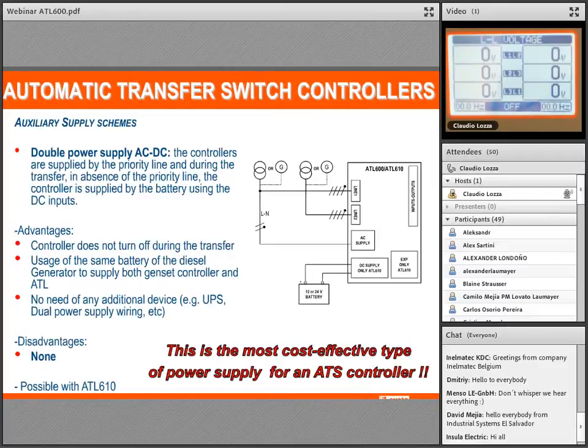What does it mean? The AC supply is present from the line 1 or the primary line, because you can select the primary line inside the setup. So the controller doesn't turn off during the transfer, because when the primary line is absent, the controller changes the power supply from the AC side to the DC side. So the battery is not used if the AC is present, but is used only in case of emergency, so during the transfer. So there is not any disadvantage for this application. And it's possible only with the ATL610.